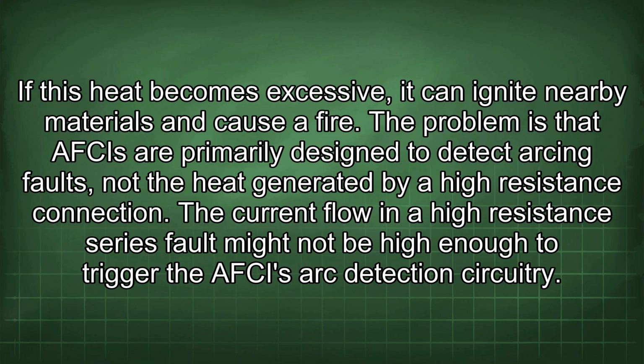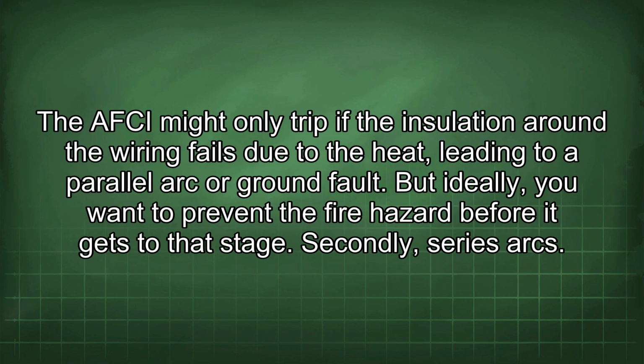The problem is that AFCIs are primarily designed to detect arcing faults, not the heat generated by a high-resistance connection. The current flow in a high-resistance series fault might not be high enough to trigger the AFCI's arc detection circuitry. The AFCI might only trip if the insulation around the wiring fails due to the heat, leading to a parallel arc or ground fault. But ideally, you want to prevent the fire hazard before it gets to that stage.